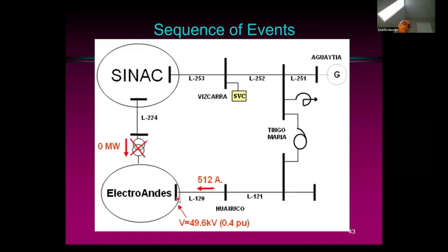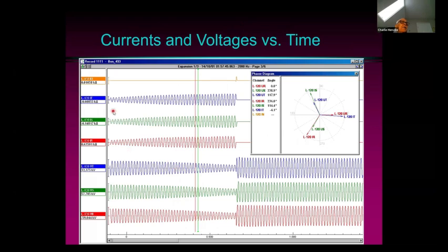But because it was a modern protective relay that monitored or recorded the voltages and currents that it was seeing, we got a recording of the voltages and currents at this point. So we see here the three-phase currents gradually getting bigger and bigger, and the three-phase voltages gradually getting smaller and smaller until the line trips, and then the current goes down to zero, and the voltage goes back up to normal or even slightly higher.